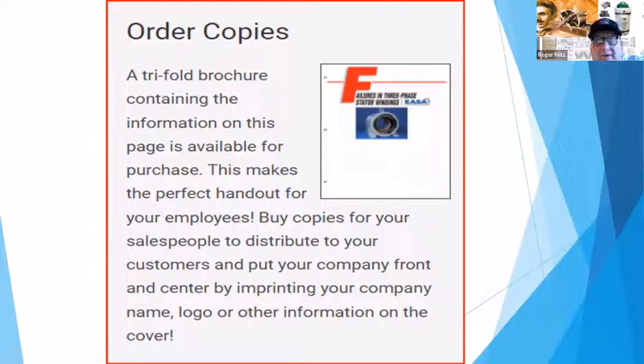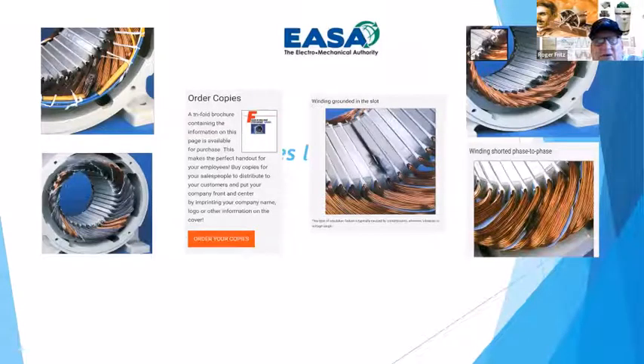There's also a manual available from EASA, which is about motor failure. And again, motors tell the story. So this shows a failure inside of a motor that was from a quick surge of voltage and power in one phase. And you can see that the high voltages between these insulated wires ended up being higher than normal. So it shorted, an internal core short.